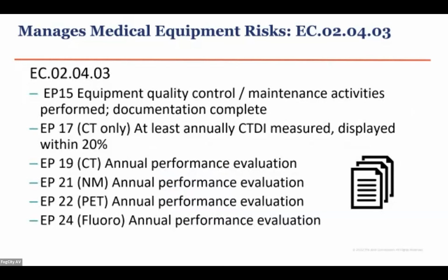EC 02 04 03 pretty much says, well, you made the plan, now follow it. So EP 15 says that you're following your maintenance quality assurance quality control plan and that you're documenting that you're doing it. So they're going to ask to see the reports. And then we have a couple of EPs that are focused on CT only in the imaging armamentarium. And then there are some that focus on nuclear medicine, PET, and then our latest kind of dip is into fluoroscopy. So you notice there's nothing here that just deals with straight radiography.